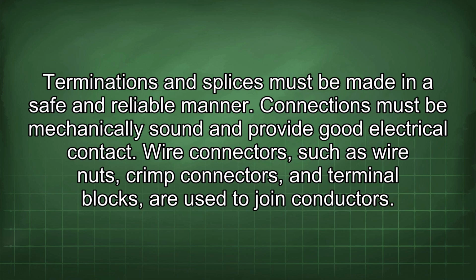Terminations and splices must be made in a safe and reliable manner. Connections must be mechanically sound and provide good electrical contact. Wire connectors, such as wire nuts, crimp connectors, and terminal blocks, are used to join conductors.